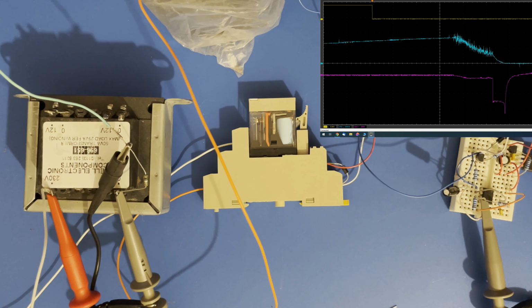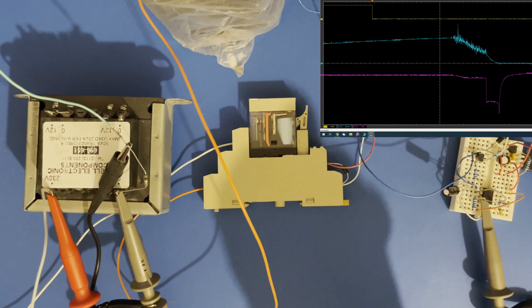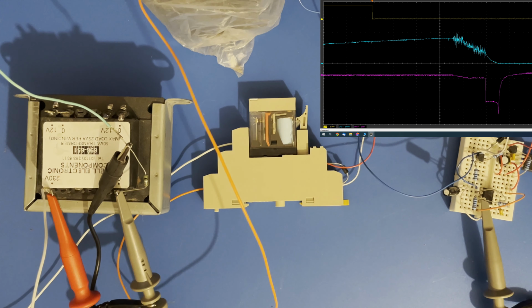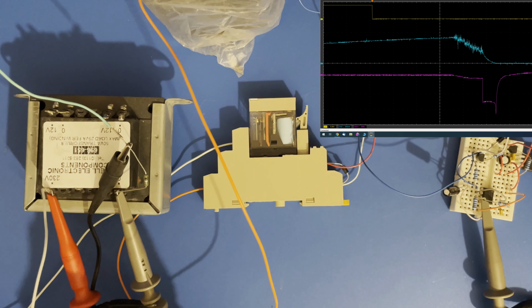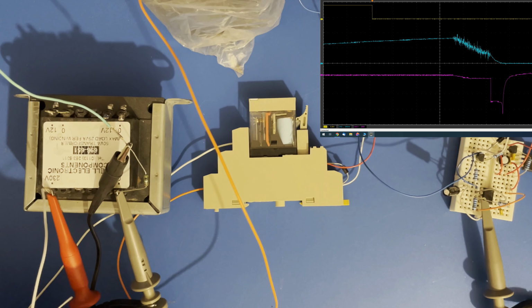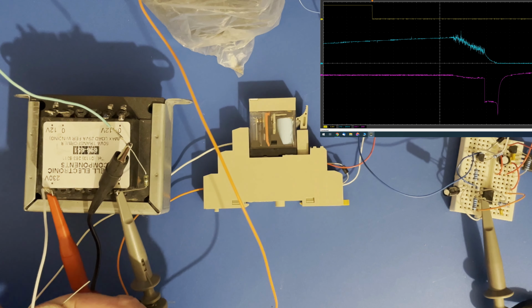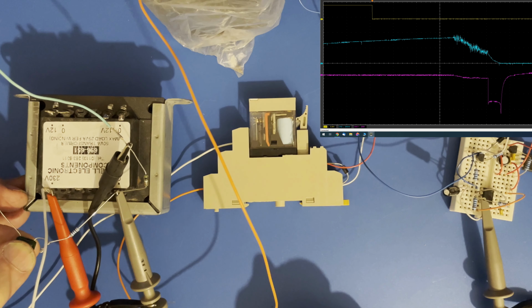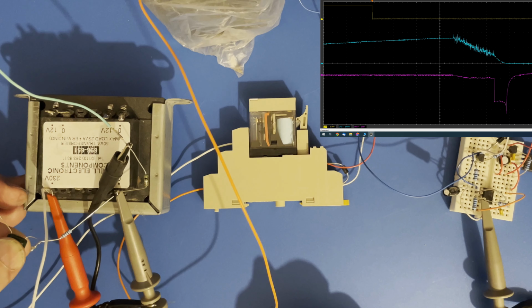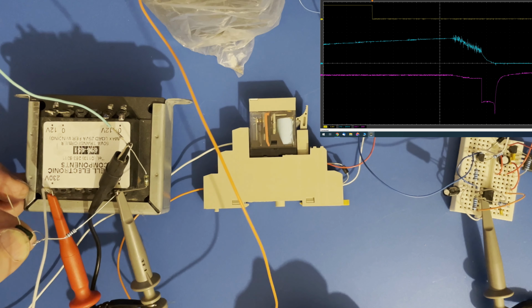Right, it's 100 ohms. Normally these are used with AC circuits, because the properly designed ones can be connected across AC power without any harm. So they can be connected across a coil whilst it's powered, and they just absorb the spike when the contact's feeding it open, without any other real effect - it's minimal power dissipation.